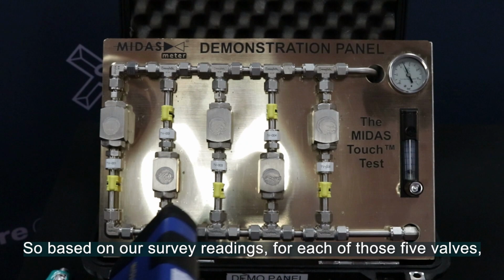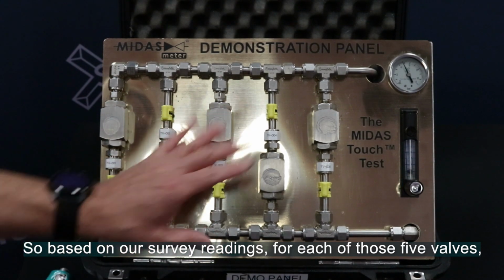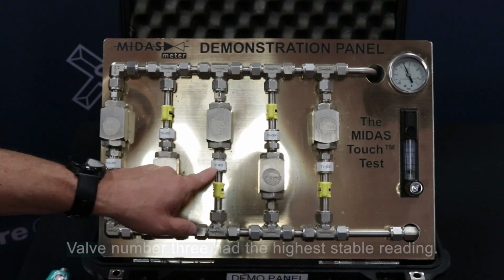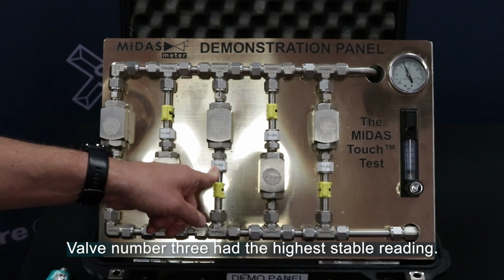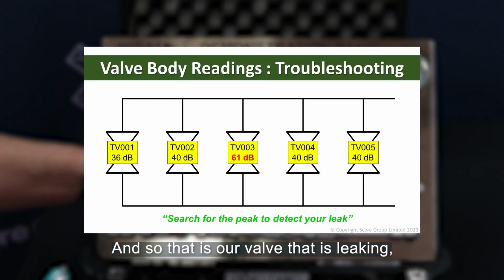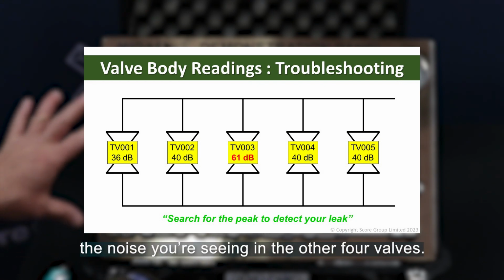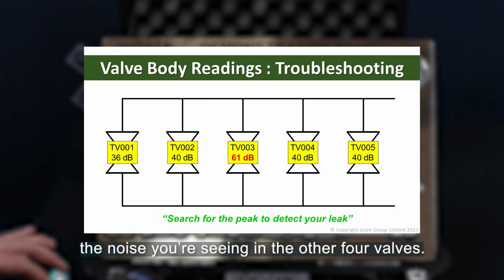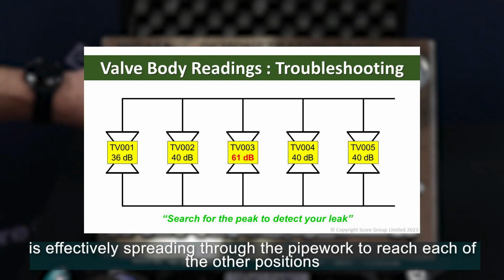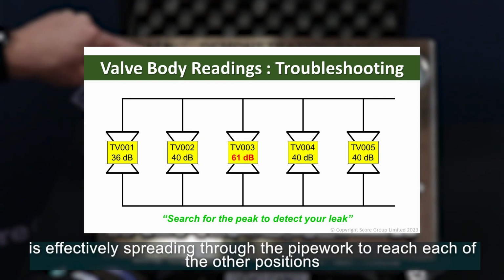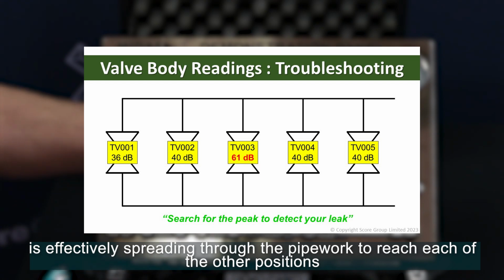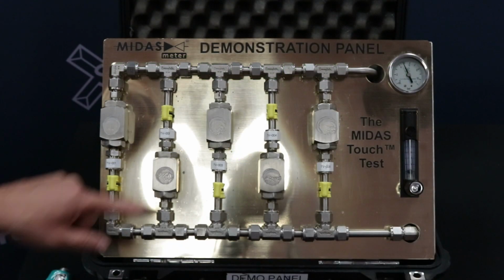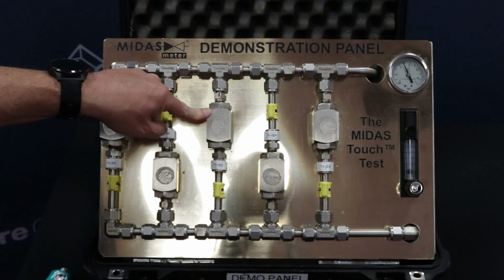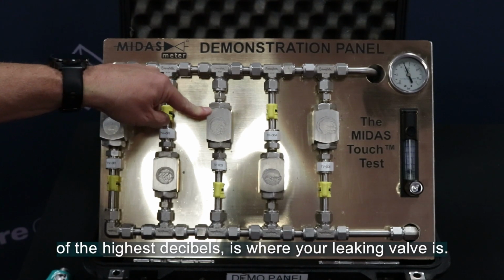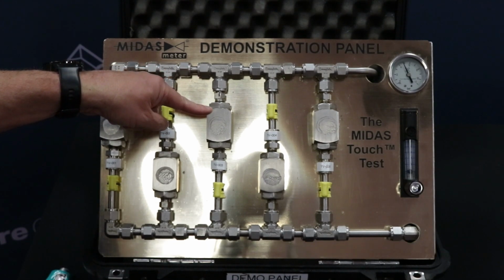So based on our survey readings for each of those 5 valves, valve number 3 had the highest stable reading, and so that is our valve that is leaking. The noise you're seeing in the other 4 valves is effectively spreading through the pipework to reach each of the other positions. The source of the highest decibels is where your leaking valve is.